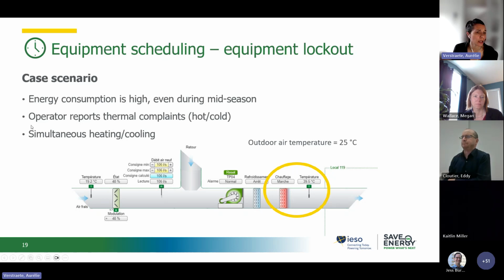In that example, we have a heating coil that is on during summer with a supply air temperature at 39 degrees C. So there is a problem here. It was a very hot summer day and your heating is on, so maybe something is wrong, but still you want to avoid that situation and maybe establish an equipment lockout on heating coils during summer.